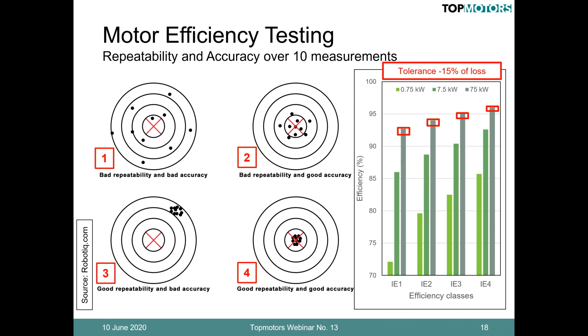And the bigger the motor, the higher the efficiency. If you go to IE3 or IE4 machines, these tolerance bands are very small. That means, going back to the left part of the graph, you really need a testing method that is agreed internationally, and that secures that you have good repeatability and good accuracy. That's the reason why testing is such a sophisticated procedure. I'll show you some example. That's a motor test laboratory that also had participated in a converter test, and here is all the equipment you see. It's a picture from the Cal Test laboratory in Australia. Now, when you look at the picture on the left side here, you see the converter on the test.